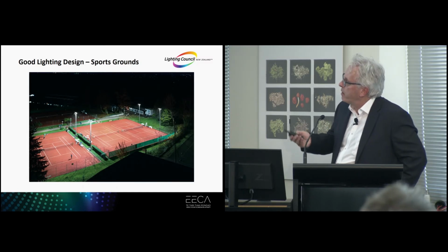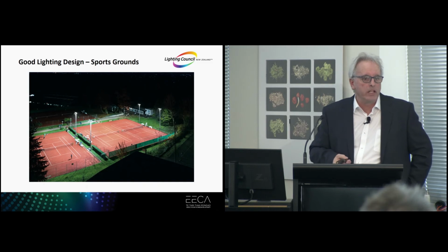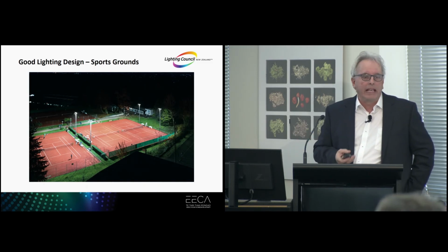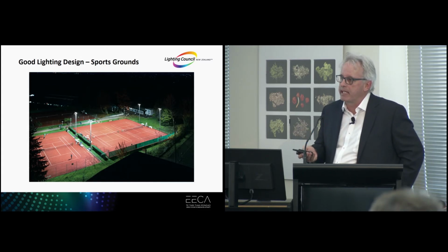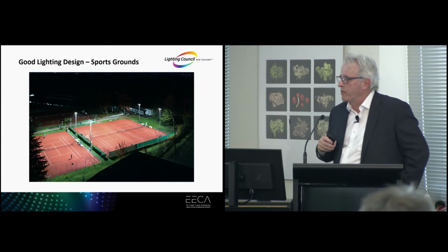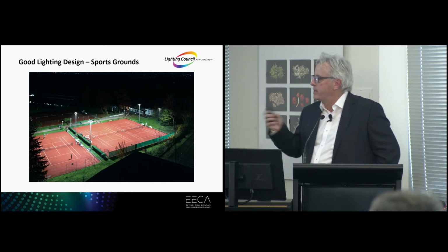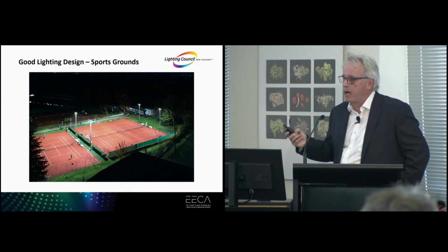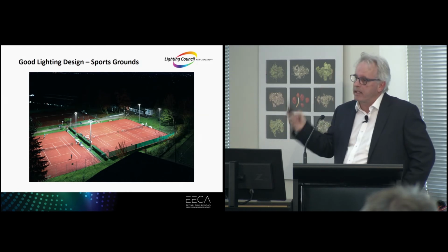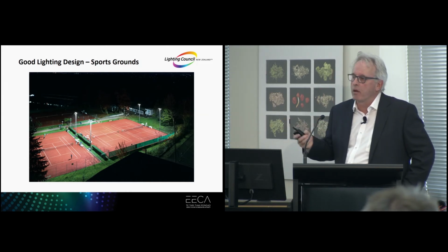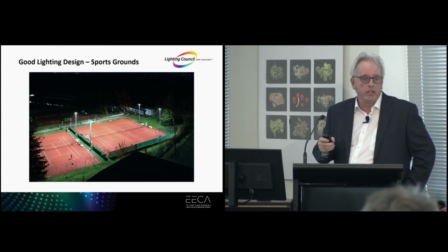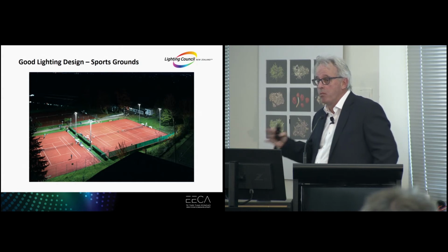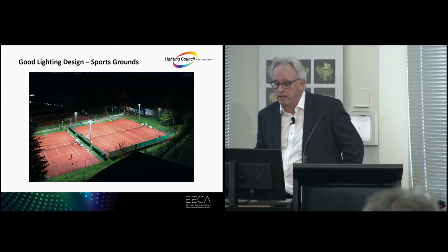But the other thing to remember is that when it's the middle of the night and there's a very, very well lit sports ground, this is where our energy is being used. Quite often the lighting of the sports ground is a lower energy use than the lighting of the nearby facilities. So councils will be saying, I've got to relight all my sports grounds, but don't only think about your sports grounds to reduce energy and carbon. It's the car parks. If you've got an Eden Park or a stadium, it's the stadium lighting. The back of house and all those areas can often be a greater energy use than the actual sports lighting. And actually there are many greater savings to be made with the associated lighting with sports and event centres.